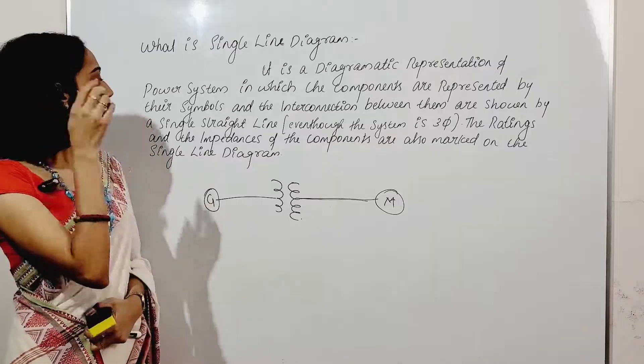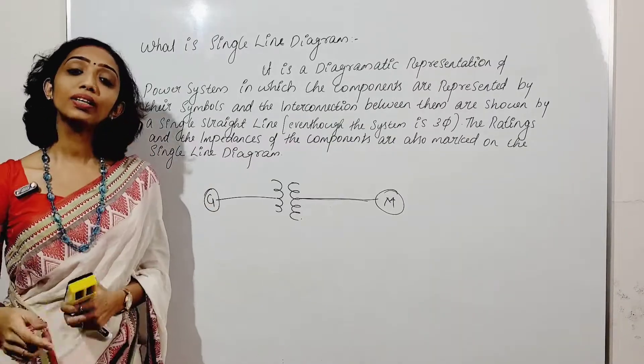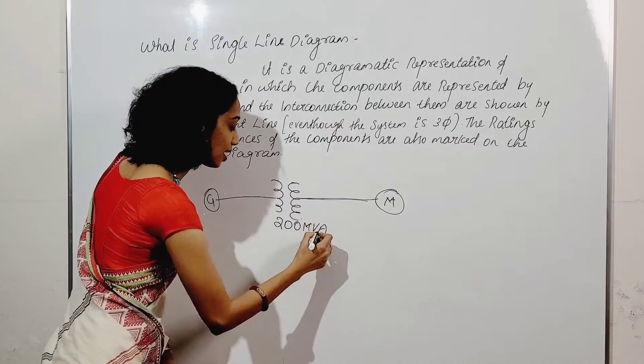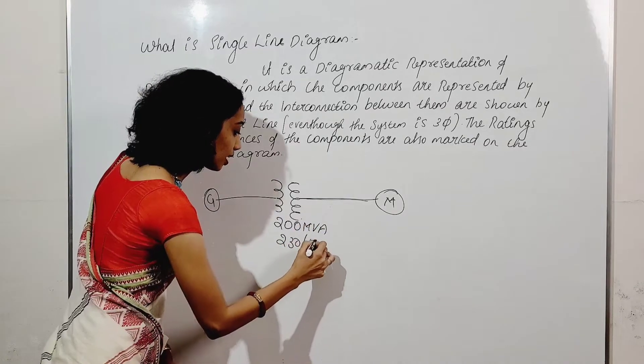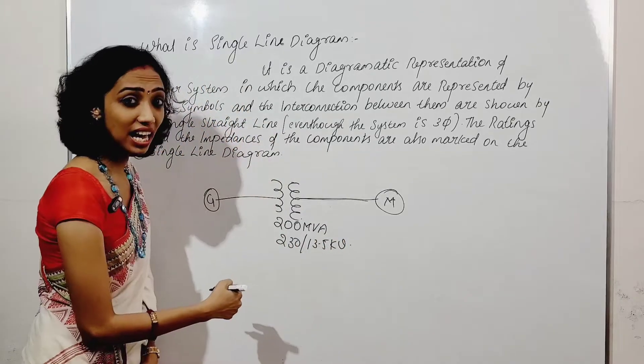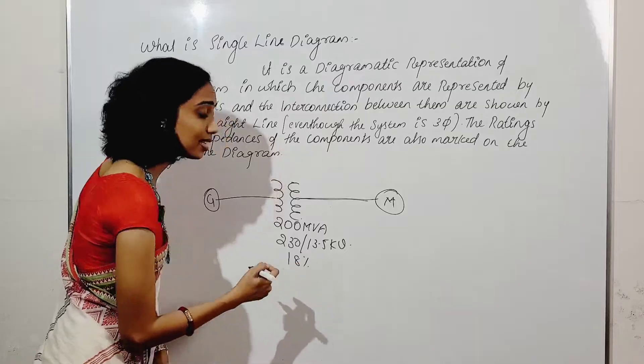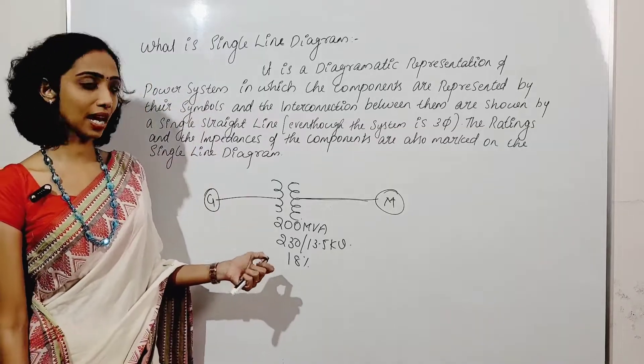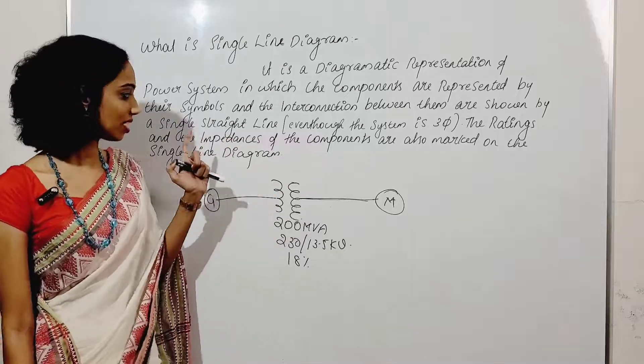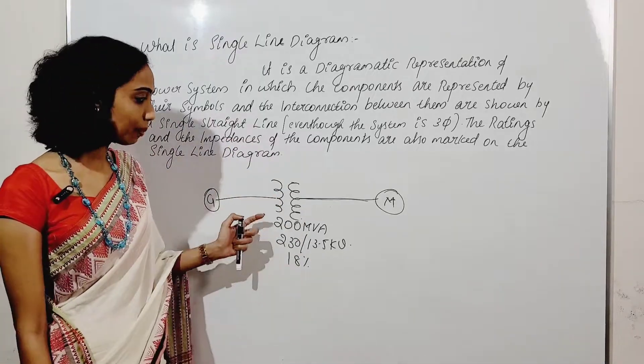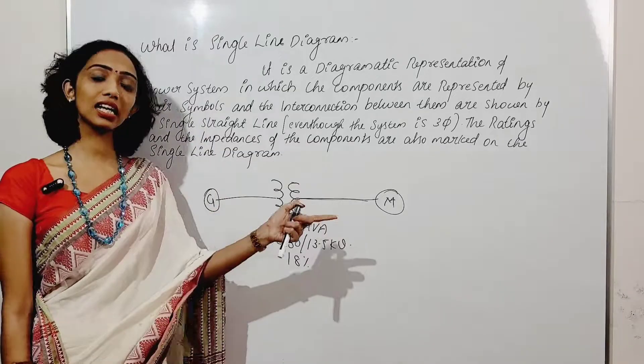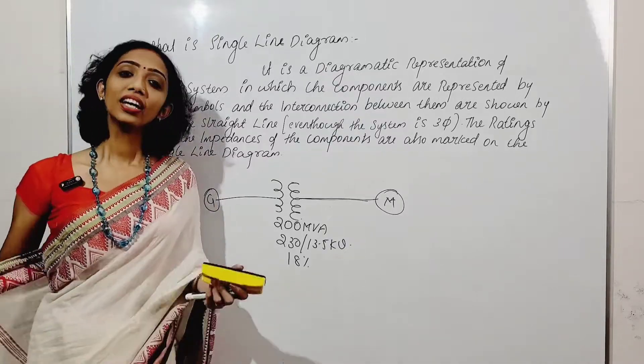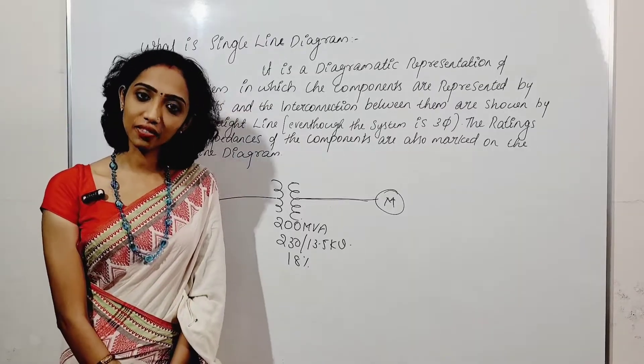The ratings and the impedances of the components are also marked on the single line diagram. For example, 200 MVA — representing the power rating — then 230 by 13.5 kV, meaning the primary and secondary voltage, and 18%, that is 0.18 per unit reactance. So we can represent the transformer, generator, and motor. This is the single line diagram, and the per unit reactance diagram is created from the single line diagram.